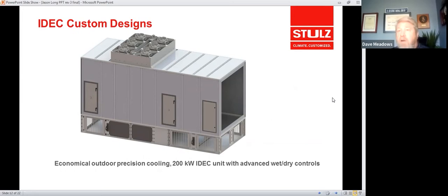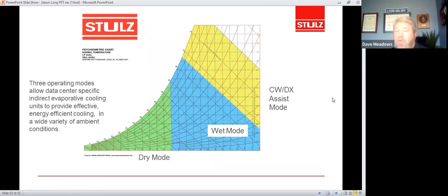In the IDEC unit, we have an air-to-air heat exchanger. So we have the cold outside air passing through the tubes of the coil, and across them we are flowing the process air that's going back to the data center. And during the cold months, we're able to operate this purely in a dry mode. In other words, the air outside is cold enough that that air-to-air heat exchanger is able to remove 100% of the heat load. Now, as the dry bulb temperature increases, say in the spring, now what we can do is we can start controlling the application of water to the outside of the air-to-air heat exchanger, and take advantage of the latent heat of vaporization.